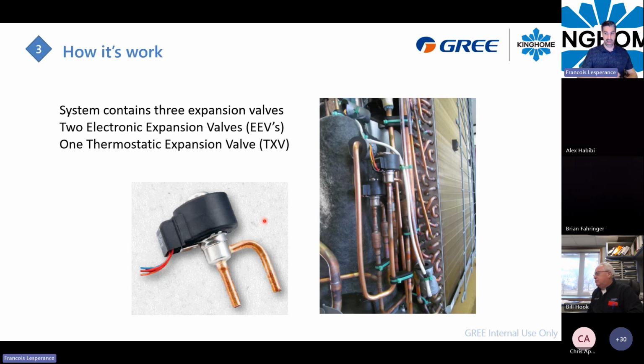So the system will manage the opening of that valve regarding all the algorithm, the temperature of the outdoor air, the temperature of the coil, and also the pressure sensor will be involved in those. The pressure transducer, sorry, will be involved in this kind of algorithm to let the system know how far it needs to open the valve or to close it.